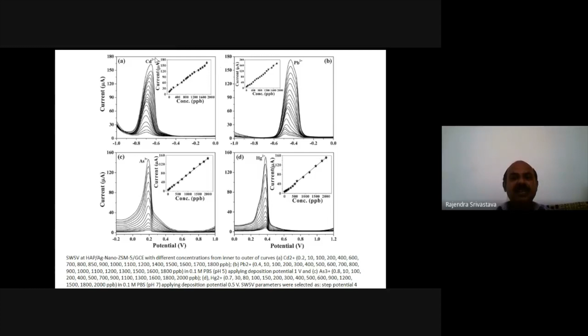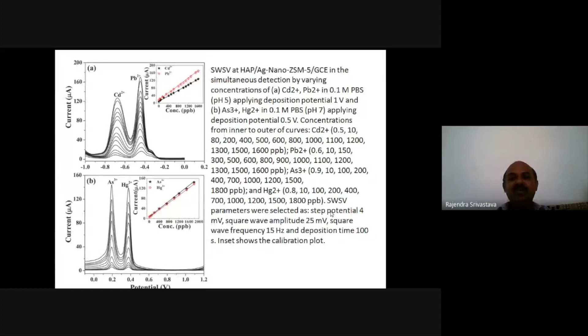So we have done it at two different pH, one at pH 5 and another at pH 7. pH 7 we used for arsenic and mercury, and pH 5 for cadmium and lead. The sensitivity is very, very good in this case. We got sensitivities of 0.1, 0.1, 0.2 and 0.2 ppb for these metals, so you can detect very low concentrations of these metal ions in the water body.